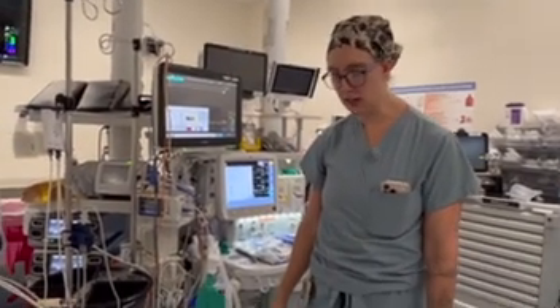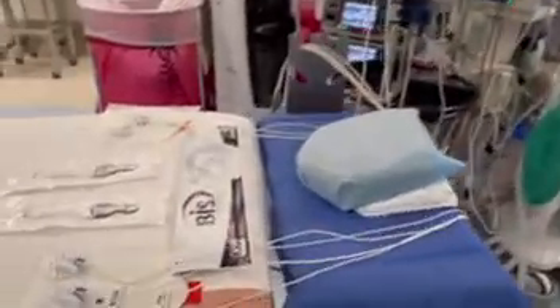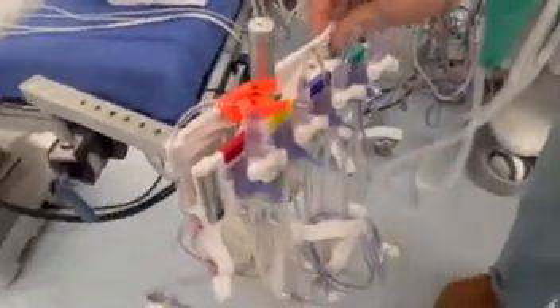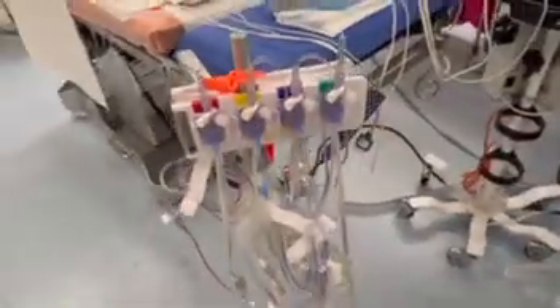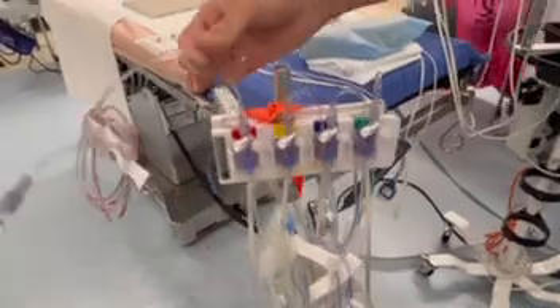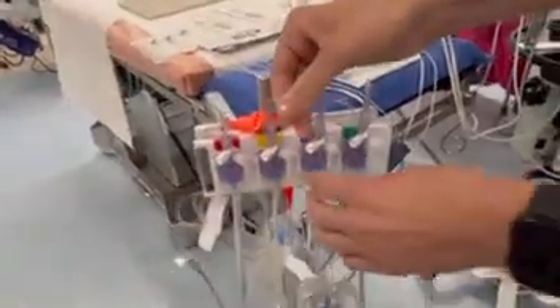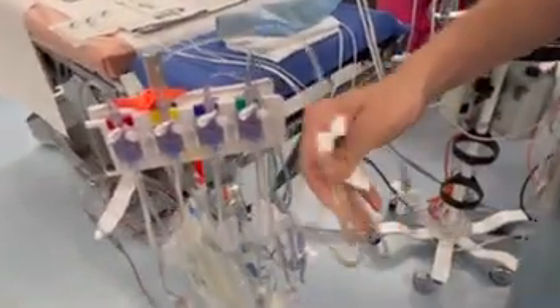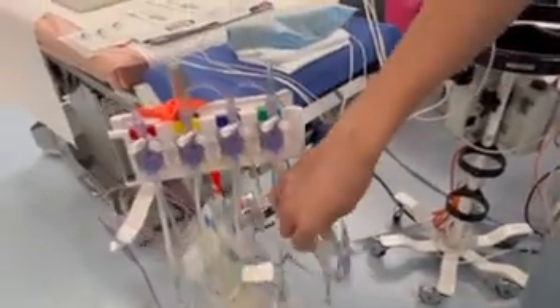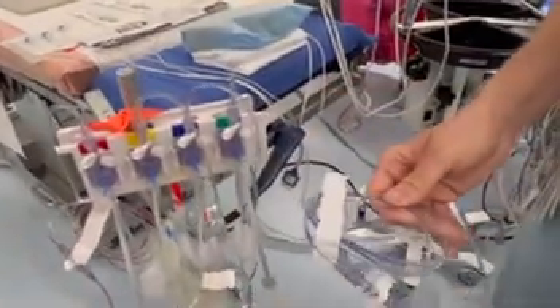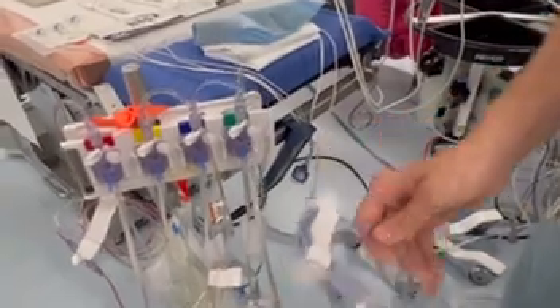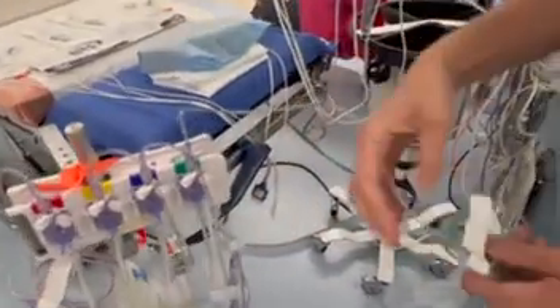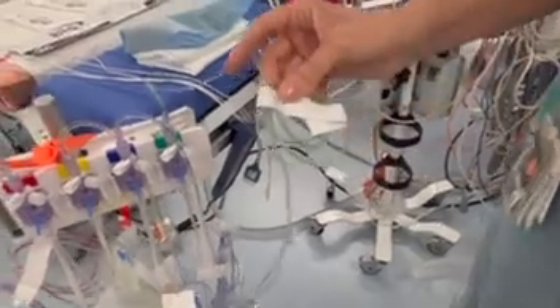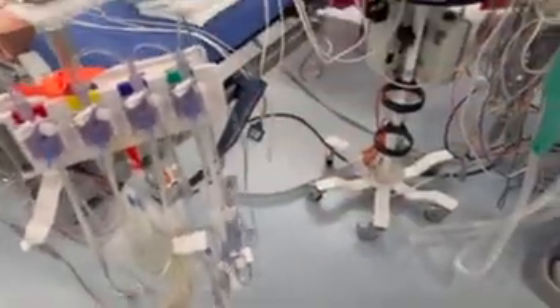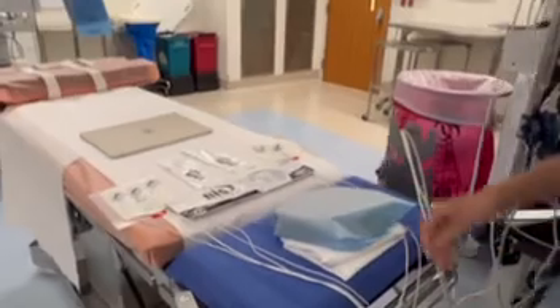Okay, next we're going to talk about the monitors that we use. So the first thing we'll look at here is our transducer setup. Anytime you do a cardiac case, we're going to have a total of 4 transducers. This is for your arterial line. If you're using a PA catheter, this yellow goes to your PA. The blue is going to go to your CVP or to a central line if you're not using a PA catheter. And this is your left atrial pressure, which is the transducer that you will use handed off from the surgical field.